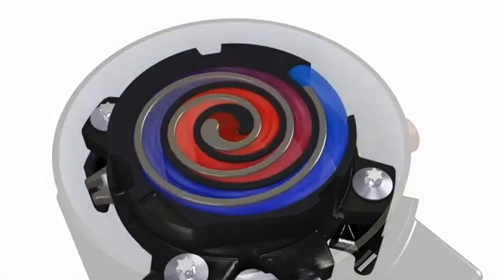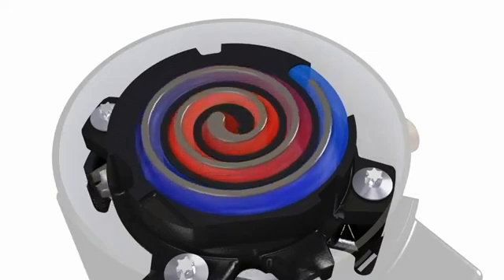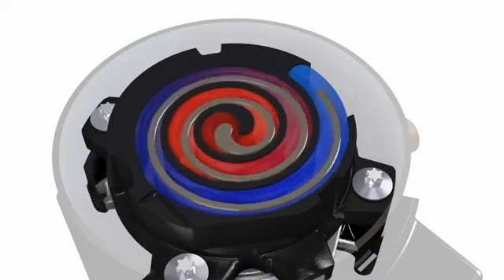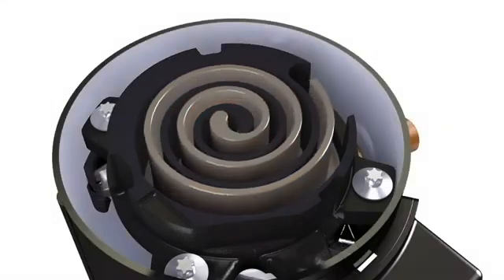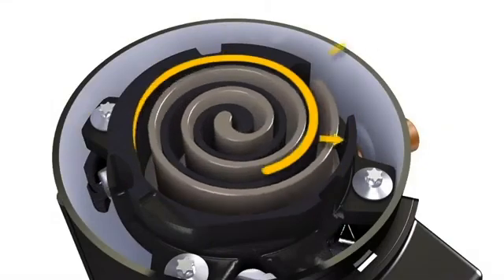A key feature of the Copeland Scroll Compressor is its ability to handle liquid refrigerant with its compliant scroll design. During normal operation, radial contact between the two scrolls is held tight by centrifugal force acting outward from the orbiting scroll.